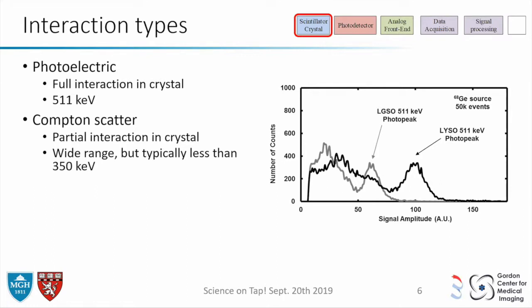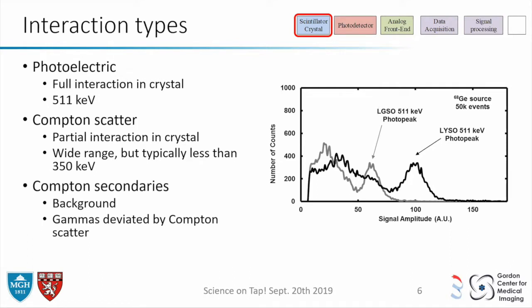Two different crystals will have different quantities of light output, so you want to adapt how you choose which events to keep. You also have Compton events that hit two different crystals. On the energy histogram — showing about 50,000 events — the scale on the bottom is how much energy an event has. You want to throw out events on the low-energy side of the graph and keep the interesting peak — those are the ones you want.